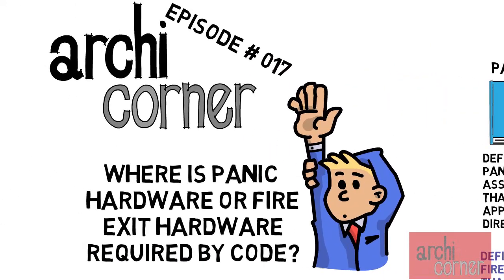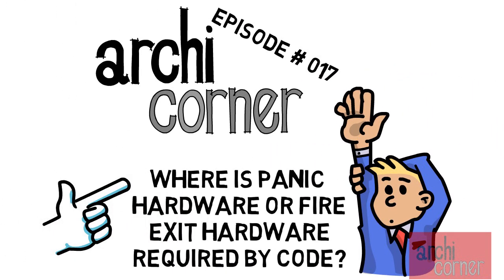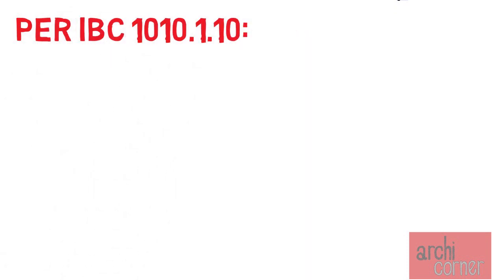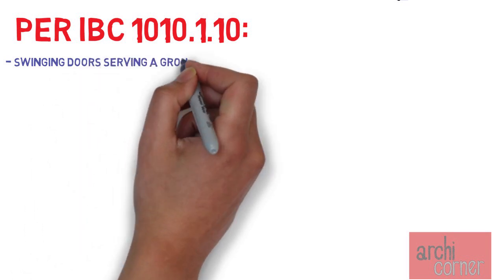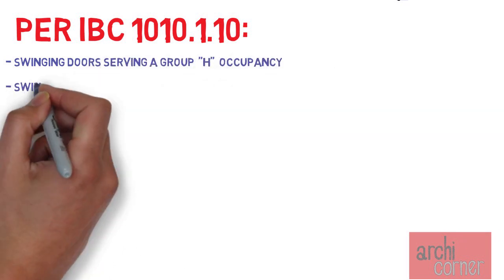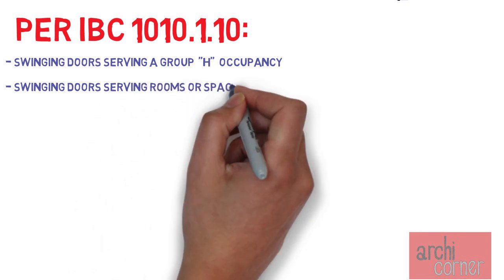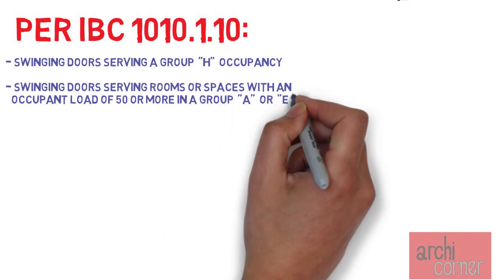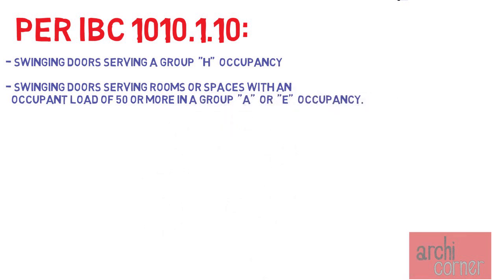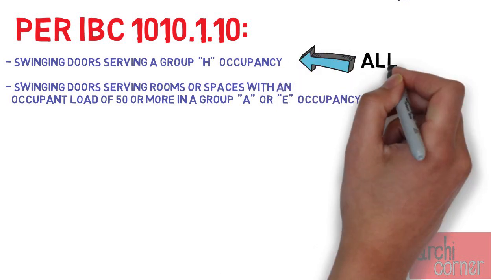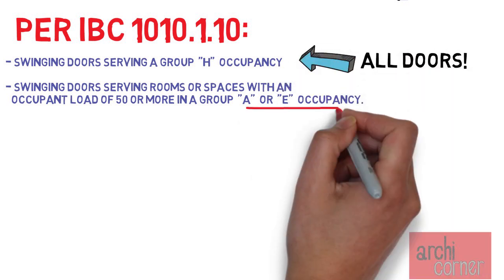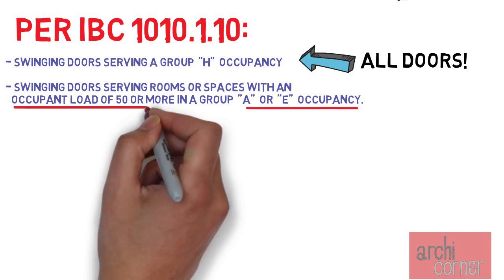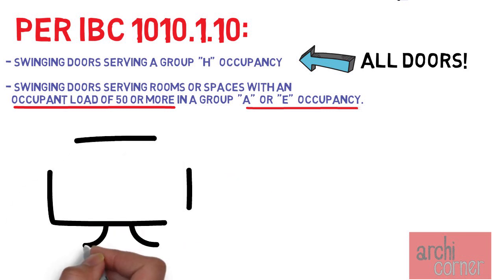So where is panic hardware or fire exit hardware required by code? IBC section 1010.1.10 states that you need panic hardware on swinging doors serving a Group H occupancy, and on swinging doors serving rooms or spaces with an occupant load of 50 or more in a Group A or E occupancy. For Group H occupancies they go on all swinging doors, but in Groups A and E they are required only in rooms and spaces with an occupant load of 50 or more.